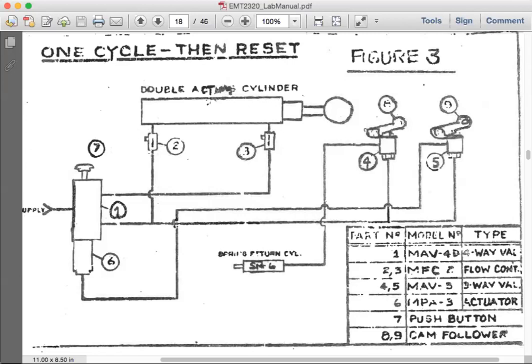So having the flow controls pointing both down, we analyze that number 2 controls the return of the piston and number 3 controls the extension of the piston. By adjusting the knob, and you see that there is no air tank here, the flow control fully controls pressurizing or depressurizing.